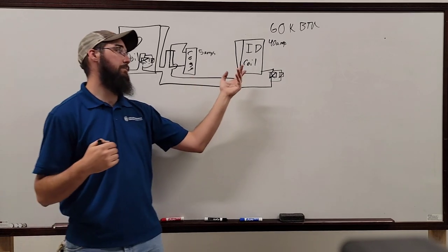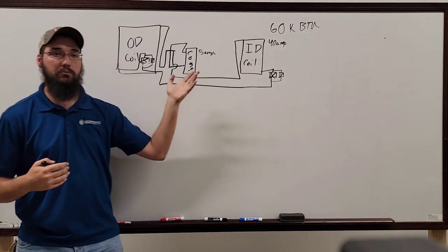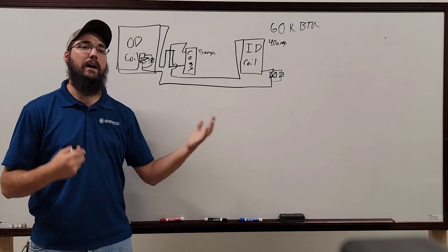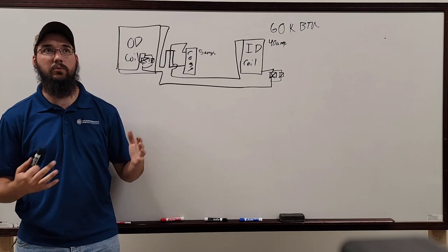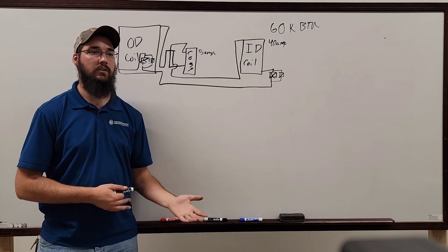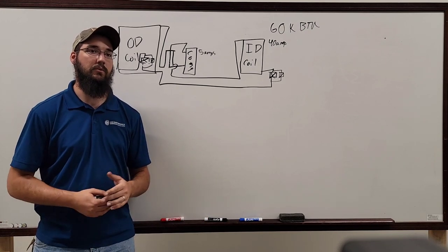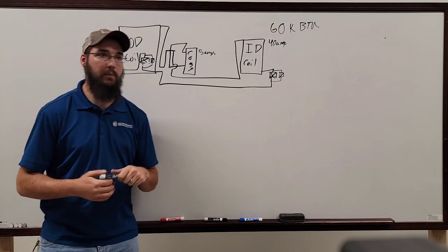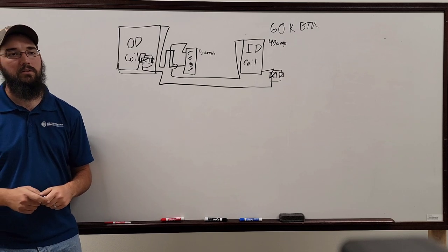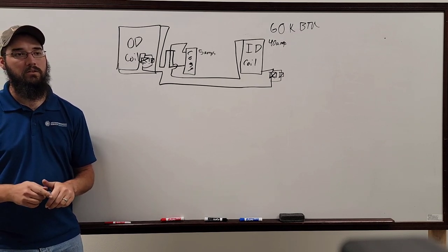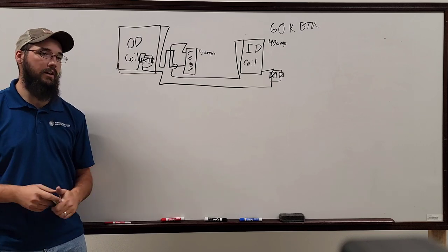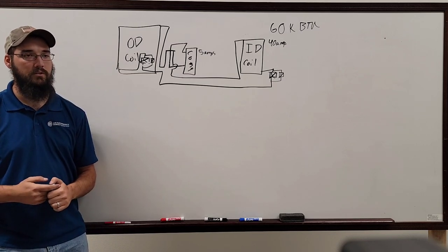And so that's where people get in trouble. They run the fan speed too low and it struggles, running too high of a head pressure in the winter season because they got the fan low. The same thing with summer, but backwards. Now, what will it cause when someone, not knowing, slows the fan down? Well, you could have high head pressure. High head pressure, yeah, and strangle the compressor.